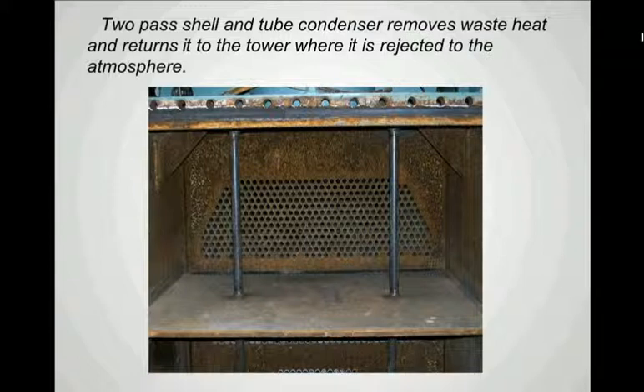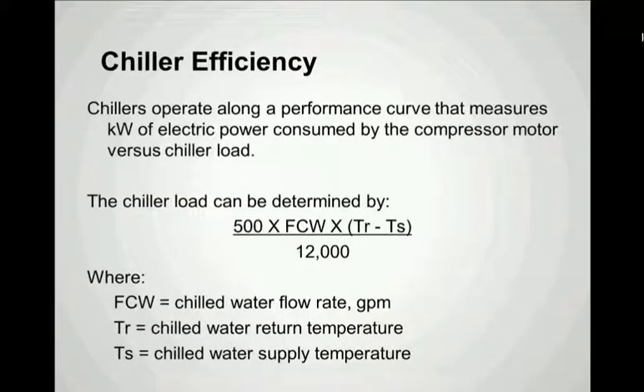So let's talk a little bit about chiller efficiency. We said along the way that chillers operate along a performance curve that measures the kilowatts of electric power consumed by the compressor motor versus the chiller load. And this concept is fairly straightforward, but very important when it comes to evaluating the overall efficiency of the chiller operation.